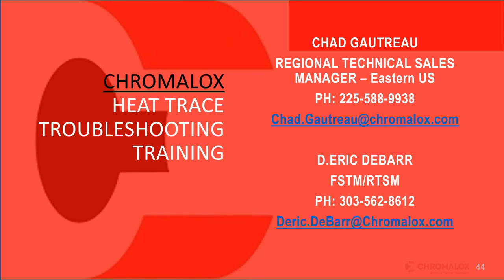Okay. The next question, and this would probably be addressed through a more in-depth dive into self-regulating cable, but a simple comment on selecting breaker size for SR cable. Yeah, so typically we depend upon Chromatrace to do that for us. If you put all of your data in there, the circuit length, the pipe size, the insulation types and thicknesses, then the software is going to pick the appropriate breaker. It's not going to let you pick an undersized breaker for that application, and it's only going to let you choose a breaker that's at 80% of its rating. So you don't want to manually do that. You've got to run the calculations to figure out what your inrush is and what your steady state current is. So we depend upon our Chromatrace software to pick those breakers for us.